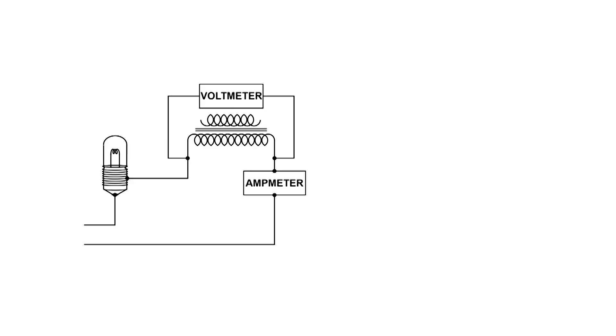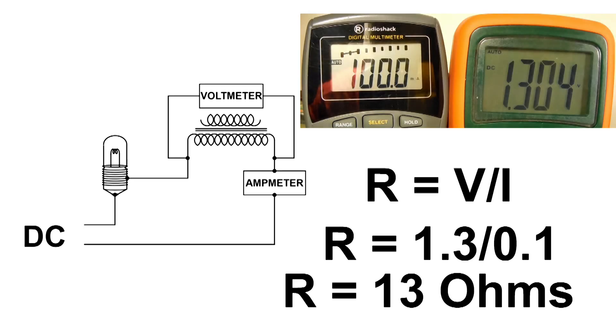Let's take a look at the results. This is the DC result. At 100 milliamps we ended up with 1.3 volts DC. Putting that into the formula R equals voltage over current, we end up with 13 ohms when we run DC through that primary.